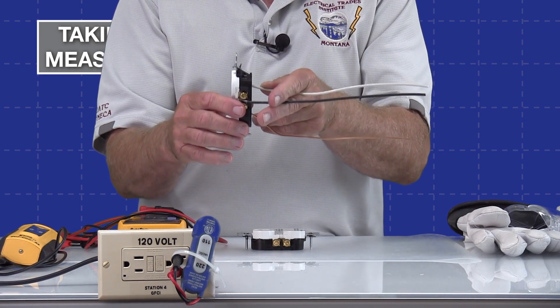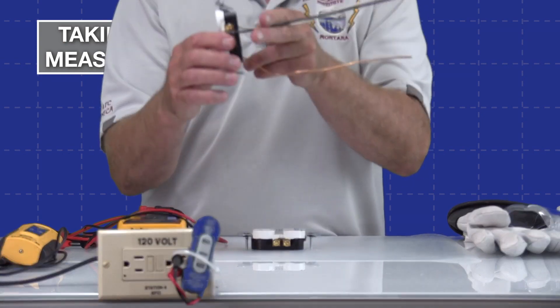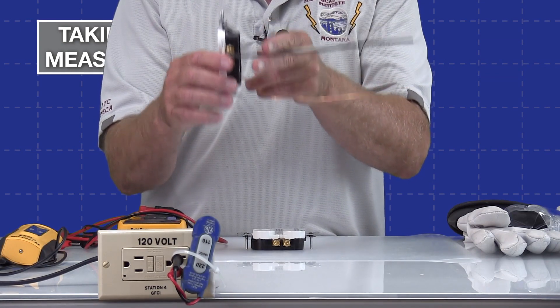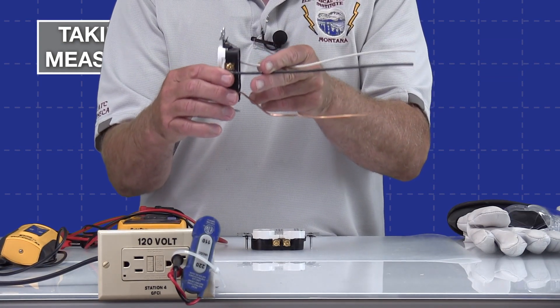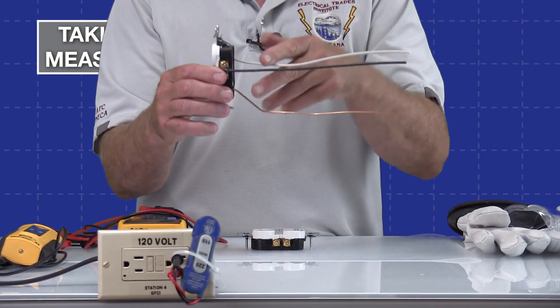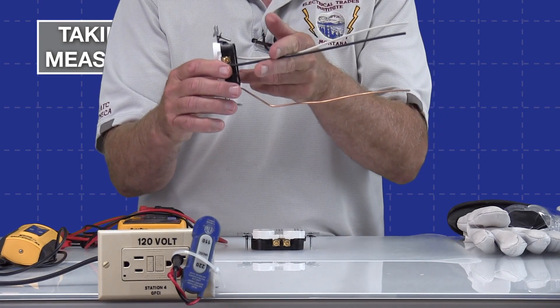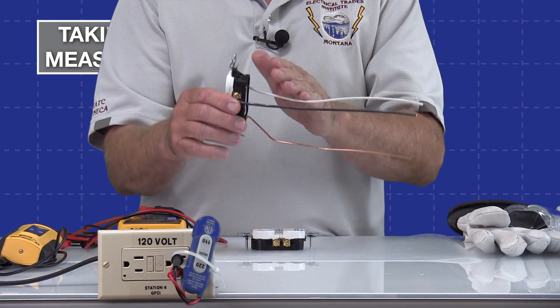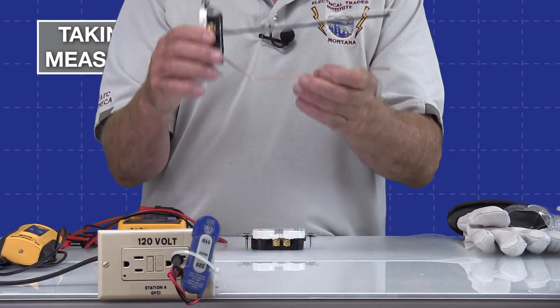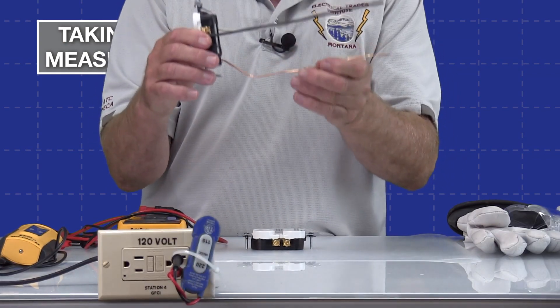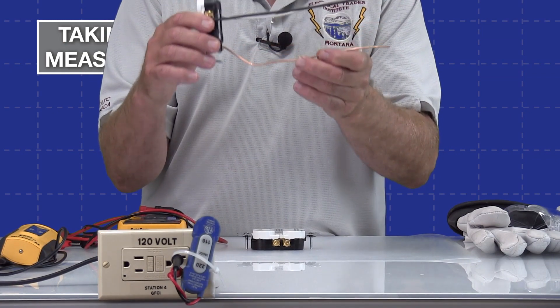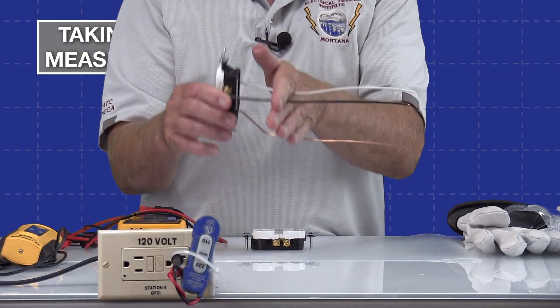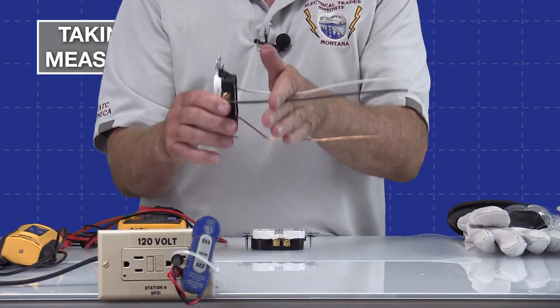In the case of these GFCIs, they will trip if there is an imbalance of four to six milliamps. So it's very sensitive. You have to have the same amount of current on both wires. If there is not, the GFCI assumes there is a ground fault or current leaking on the ground, and it will trip and interrupt the circuit. On a GFCI, the equipment ground does not need to be there to carry the ground fault current. It really looks for the imbalance on the black and the white wire.